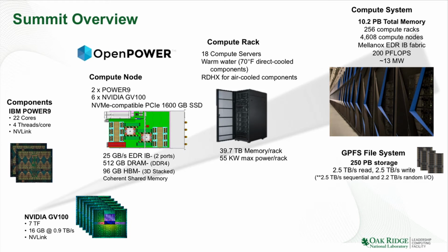For each compute rack here, one of the interesting things about Summit, this is the first time we've gone with a warm water cooling system. And for mechanical engineers, that's a really innovative solution. Titan is water cooled as well, but it's chilled water. With Summit, we only have to have 70-degree water, which is much warmer than what you would find in most data centers.